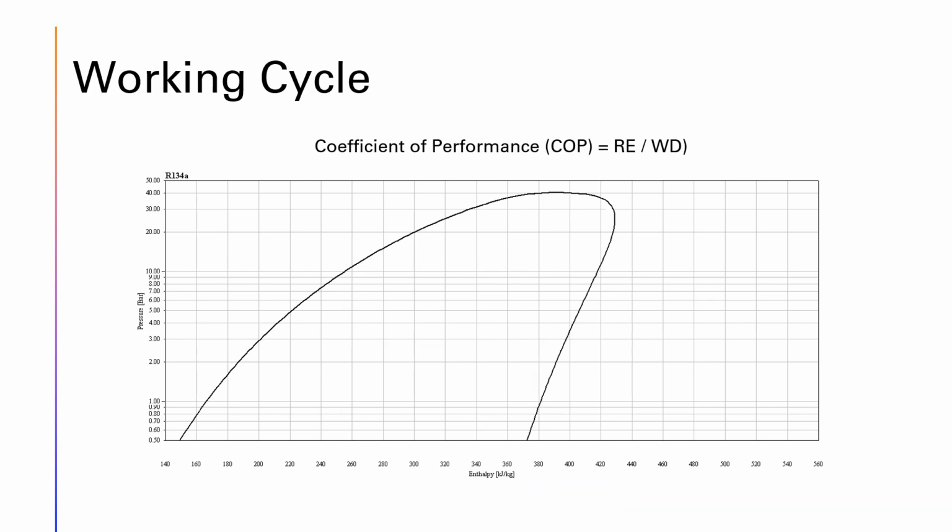Okay, so that was a theoretical cycle. Let's have a look at a more realistic working cycle. We start off again with the compressor. We're raising temperature and pressure into the condenser, where it's turning slowly back from a high pressure gas to a high pressure liquid. That then enters the expansion valve, where there's a massive pressure drop but no real change in temperature, and it then goes into the evaporator. Now, as it's moving from left to right, it's gaining heat and boiling back to a gas, and hopefully when it goes back into the suction of the compressor, it's purely superheated.